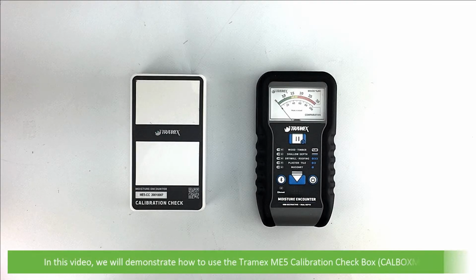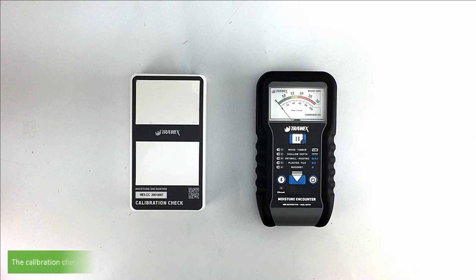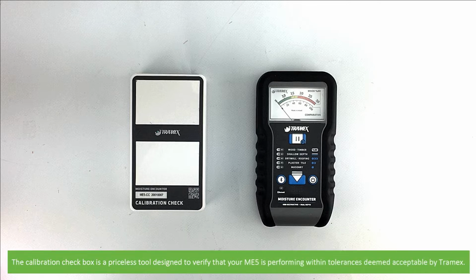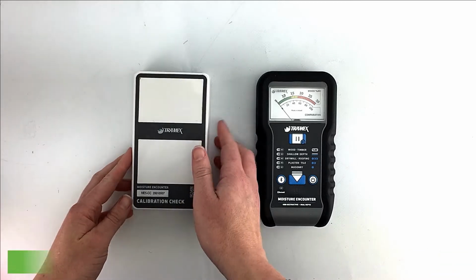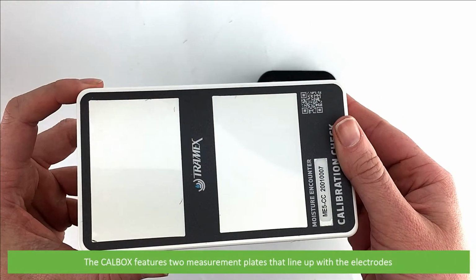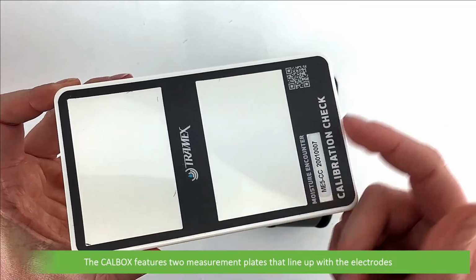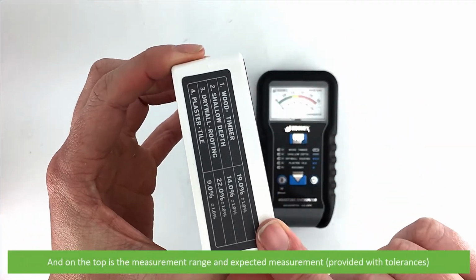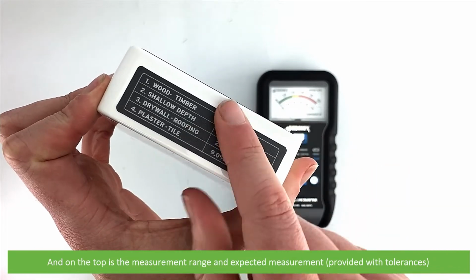In this video, we'll demonstrate how to use the Tramex ME5 calibration checkbox, the CALBOXME5. The calibration checkbox is a priceless tool designed to verify that your ME5 is performing within tolerances deemed acceptable by Tramex. The CALBOX features two measurement plates which will line up with your ME5's electrodes, and on the top is the measurement range and expected measurement provided with tolerances.